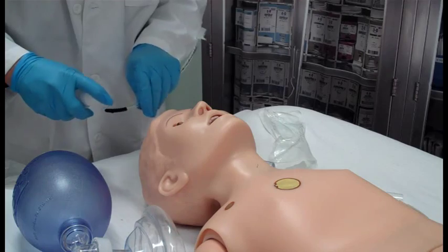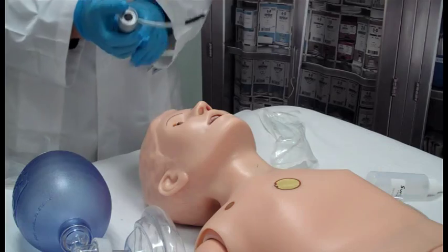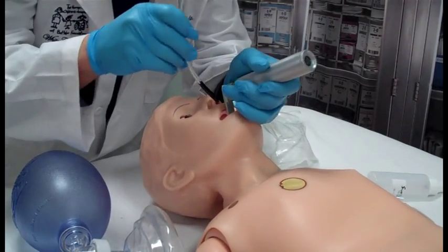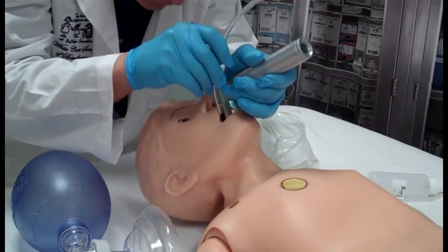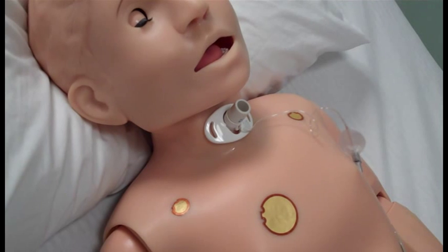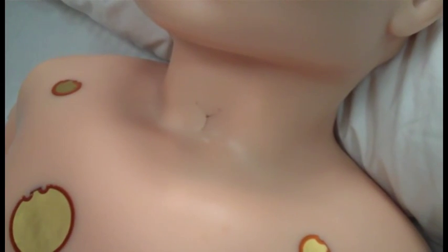Ralphie can be intubated orally and nasally through his left naris, although you may need to lubricate the airway adjunct with silicone oil prior to any intubation attempt. Please do not use lubricating jelly on any of the mannequins as it is very difficult to clean the airways. A tracheostomy tube can be placed in the pre-scored tracheostomy insertion site.